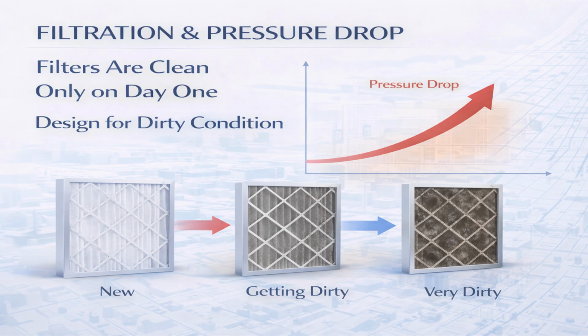One important reality in HVAC design is that filters are truly clean only on the day they are installed. From that moment onward, dust and contaminants begin to accumulate. As this happens, the pressure drop across the filters steadily increases, and the amount of air the system can deliver gradually decreases. If the fan has not been selected to accommodate dirty filter conditions, this reduction in airflow becomes unavoidable.